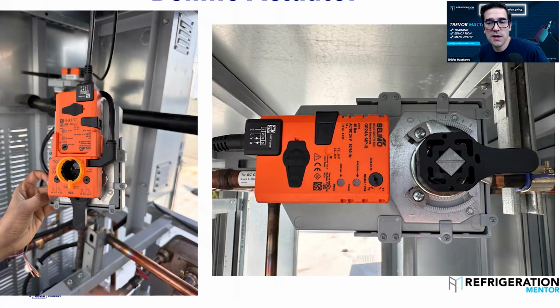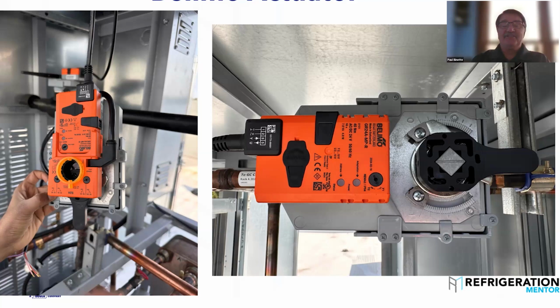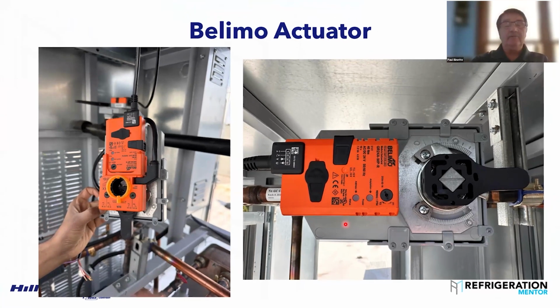Have you used any with end switches on them in these ones here? Yeah, so this rack, just getting ready to say that. On this one, Belimo has an end switch that literally fits over top of the handle, the black handle. And this was actually a pump down line for a split condenser on CO2 that we did. As soon as I saw it, I notified the factory we needed to add an end switch, because I needed to know when this valve was 100% open, and I needed to know when the valve was 100% closed, as well as the three-way valve.